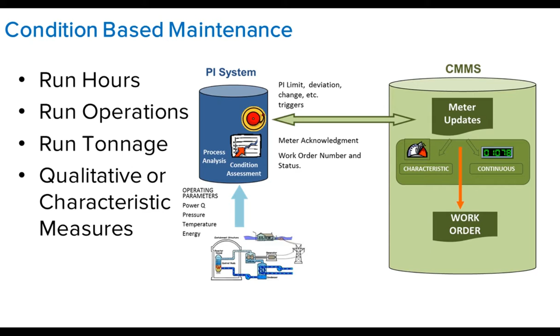An example may be detecting high vibration on a motor, or that a pump is operating consistently off its best efficiency point, or a significant differential pressure across a filter or screen. These are all cases where you'd want to notify maintenance to perform a planned function.